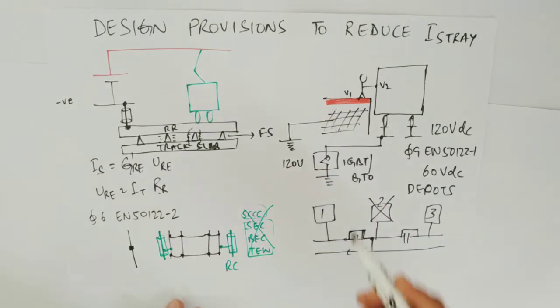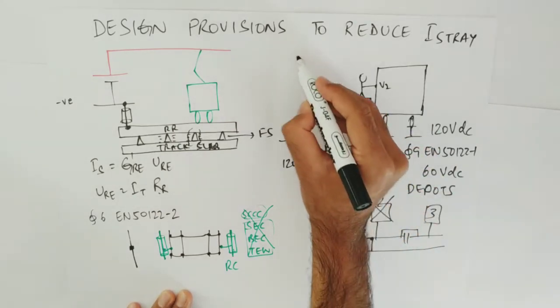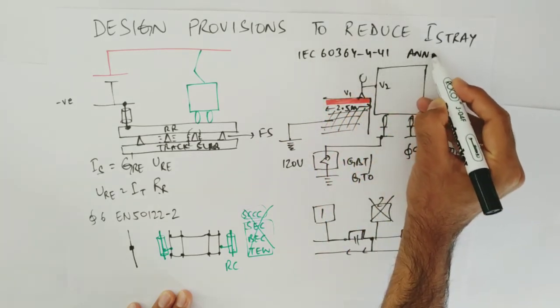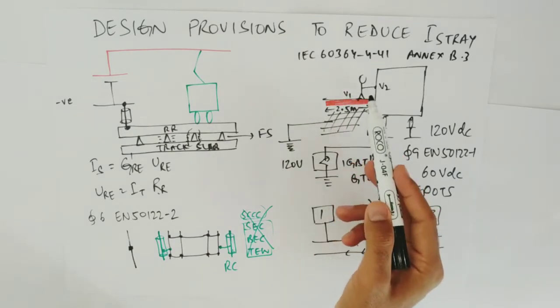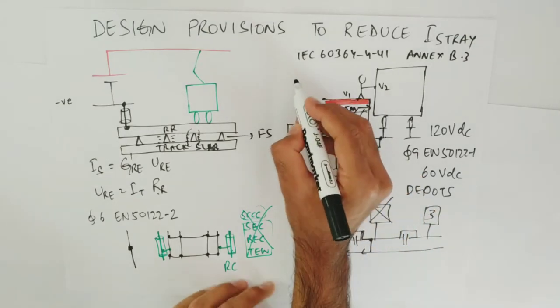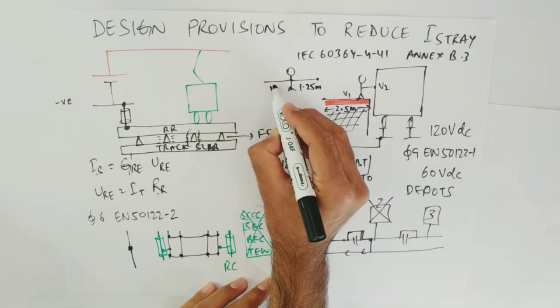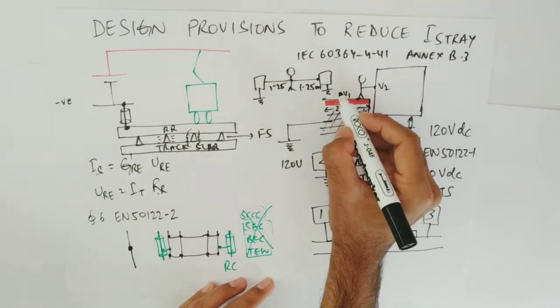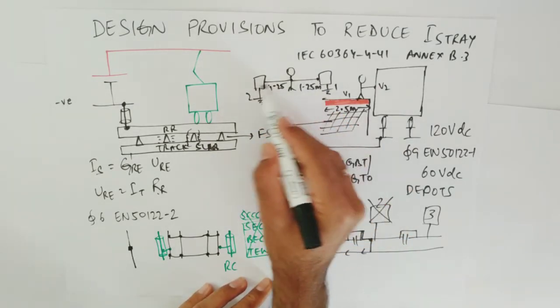This insulation membrane shall extend for around 2.5 meters. This is specified in IEC 60364-4-41 Annex B.3: if a person is touching two objects with separate voltages, the person shall maintain a distance of 2.5 meters. A person can extend each arm up to 1.25 meters, so if two objects with separate earthing systems are more than 2.5 meters apart, the person cannot touch both simultaneously.